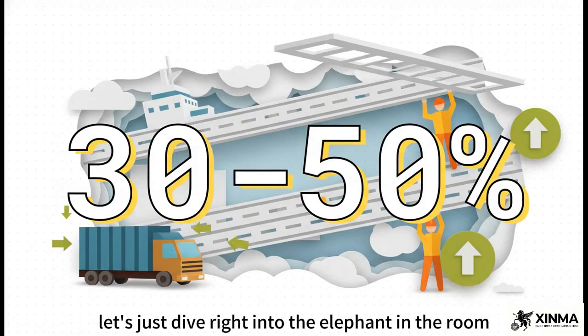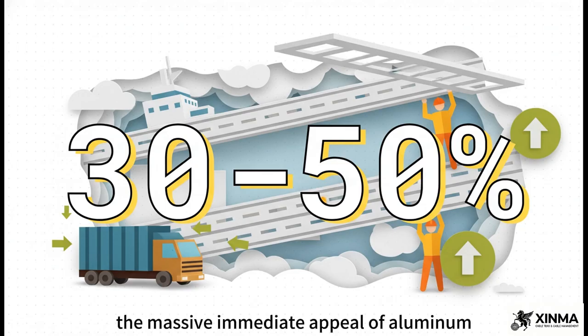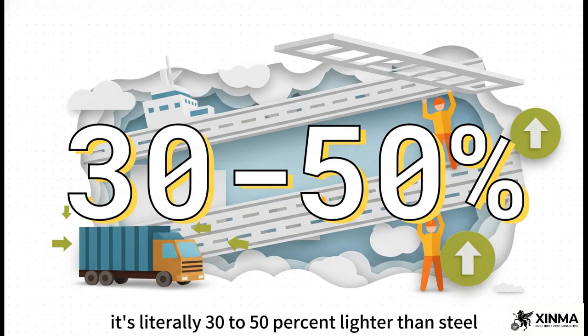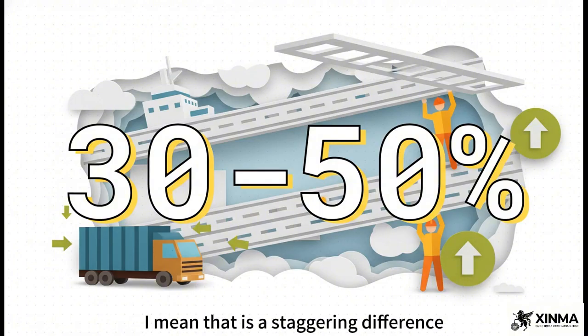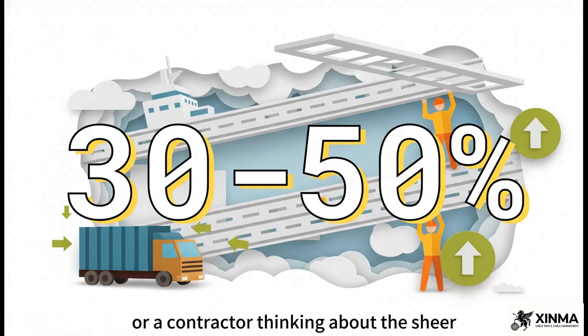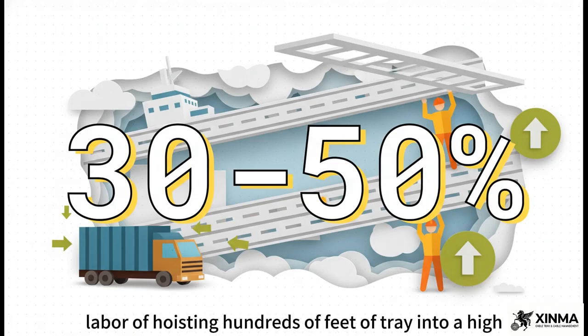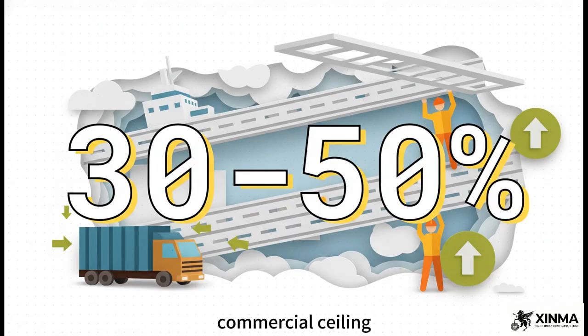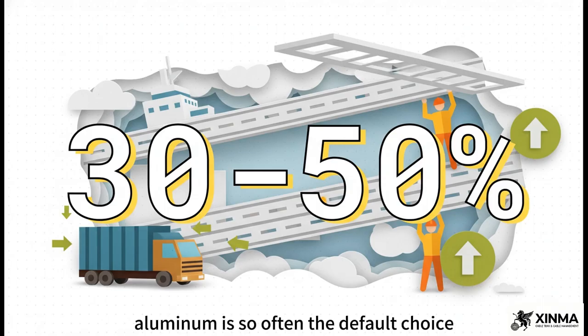Let's dive right into the elephant in the room, the massive immediate appeal of aluminum. It's literally 30 to 50% lighter than steel. That is a staggering difference. If you're a buyer stressing over freight and shipping costs, or a contractor thinking about hoisting hundreds of feet of tray into a high commercial ceiling, that number is a massive green light. It's exactly why aluminum is so often the default choice when you're first sketching out a project.